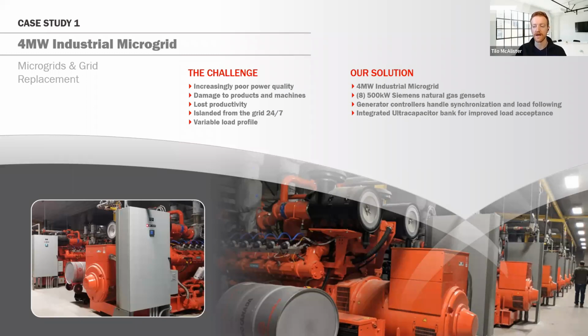The biggest challenge was that he has a huge hydraulic press that during production hours turns on every 15 seconds, causing a massive spike in demand and an inrush. If you're familiar with how reciprocating engine gensets work, they can do load following, but it's limited - there's a limit to how much load they can accept in a very short time without losing power quality and having a dip in frequency or voltage.